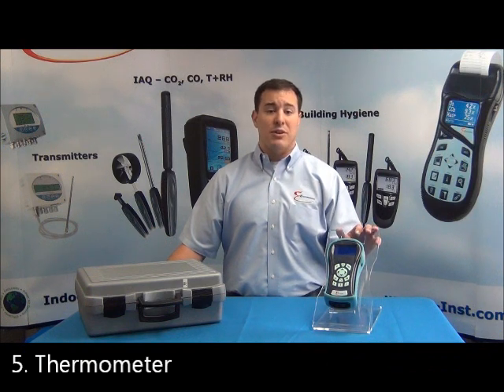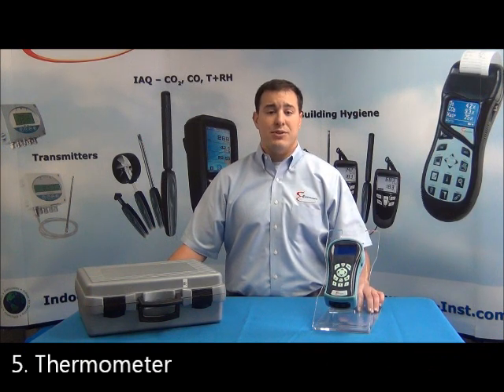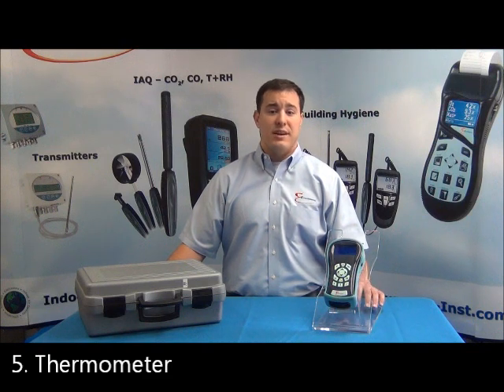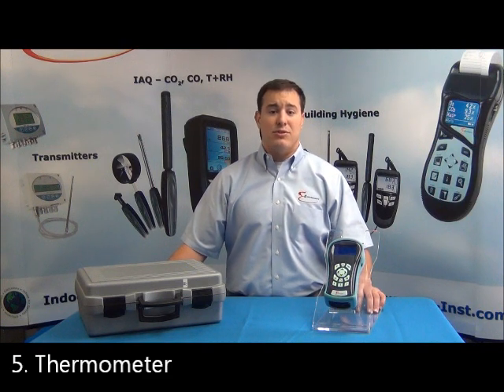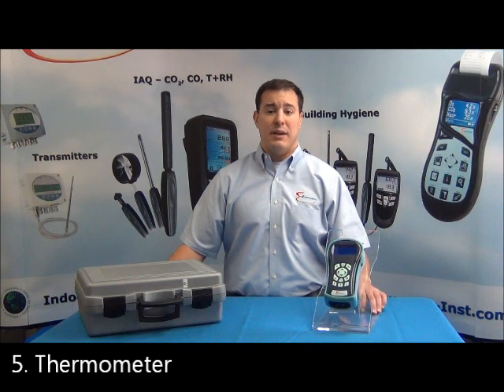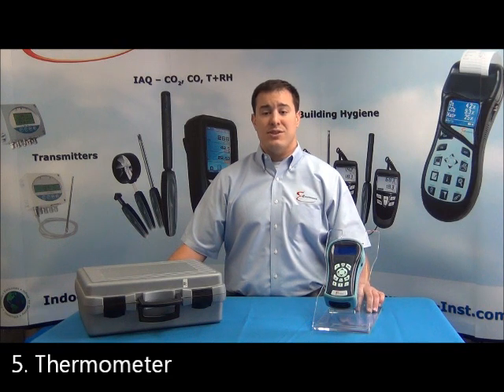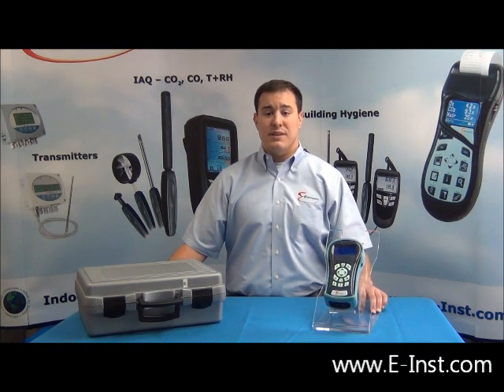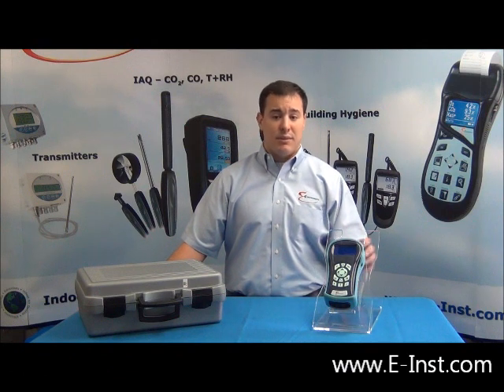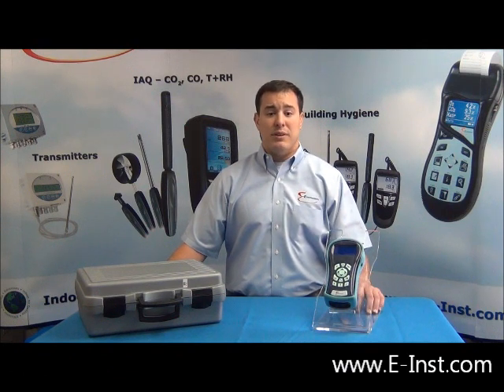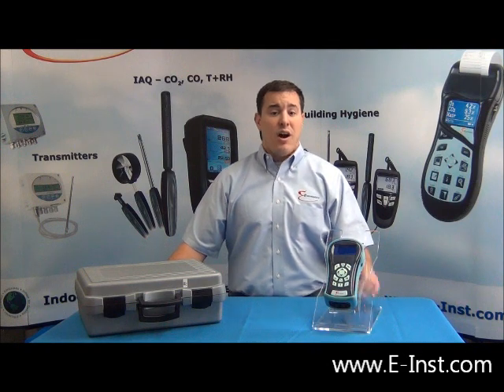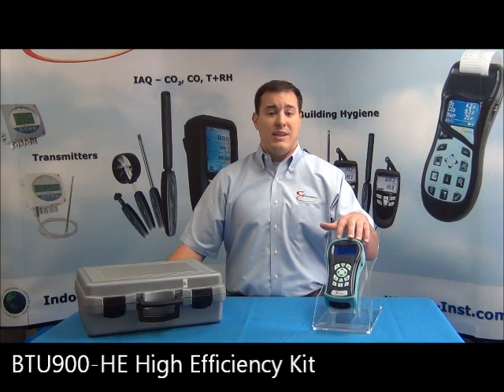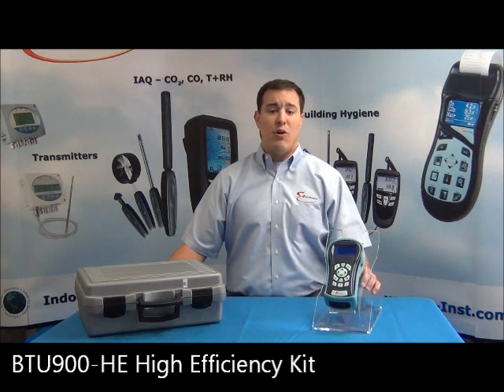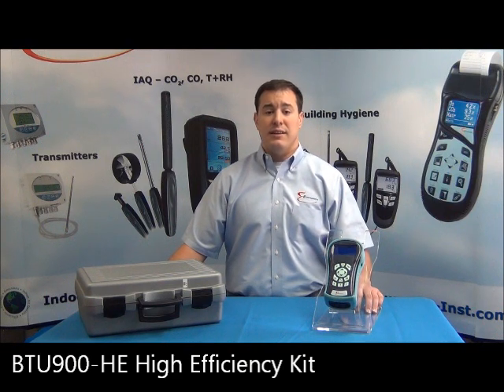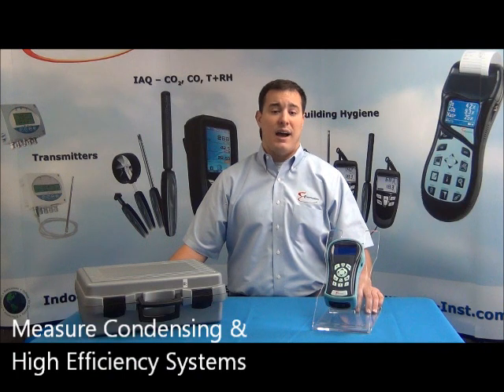Fifth and finally, it's your thermometer for flue gas temperature, ambient temperature, contact temperature, and on condensing or forced air systems. It's your incoming air thermometer to be able to properly take the temperature of the incoming air being fed to the system from the outside. This allows you to properly verify that your efficiency is correct. On condensing systems, if you are not monitoring the incoming air coming into the boiler, you're not taking the efficiency reading properly and you can get false efficiency readings. Our popular BTU900 HE high efficiency kit is equipped with all the extra probes and accessories that you will need in the field to properly measure all condensing and high efficiency systems.